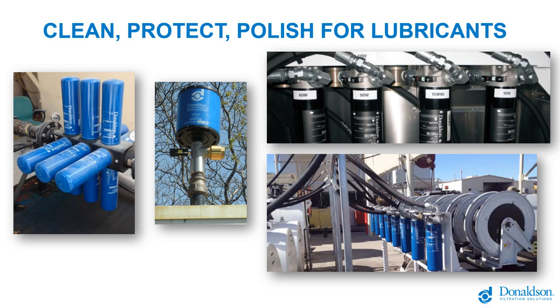But more common on the lubricant side of things are stick pumps, and those are high ratio air pumps, 3, 4, 5, 6, or 10 to 1 air pumps, and you can get pressures in operation or at a steady state of 1,000 psi, and you need a higher pressure filter. As a safety note, due to thermal expansion, where oil increases in pressure due to higher temperatures, it's recommended for these outlet systems specifically that thermal relief valves are installed. That's now a requirement by virtually every manufacturer of those style of pumps. It's a pretty common issue with those systems.